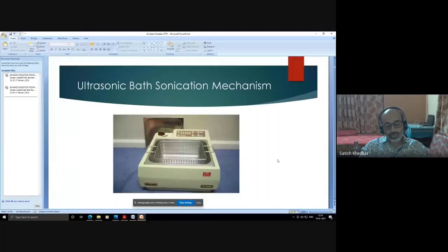So you simply place the ultrasonic bath, and after placing it, you add the medium. The medium may be water. You add the water to the ultrasonic bath, place the instruments which are to be cleaned or sterilized into the bath, and sonicate at the desired amplitude; the frequency is fixed, but you can vary the amplitude. You sonicate for the desired time, whether 10 minutes, 15 minutes or 30 minutes. After that time has been reached, you shut down the ultrasonic bath. After observation, you will find that most of the medical instruments have been cleaned.